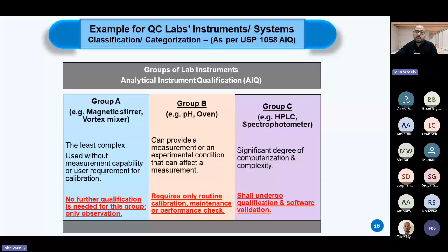And based on this, it's required more sophistication of your qualification testing, like, for example, requiring only routine calibration, maintenance, or performance check. And reaching the highly sophisticated and complex QC lab instruments like the HPLC and the spectrophotometers, here are significant degree of computerization and complexity. So we shall undergo full qualification and software validation, passing through all the qualification testing phases, starting from the URS, IQ, OQ, PQ, and all the phases that were mentioned on the previous slides.